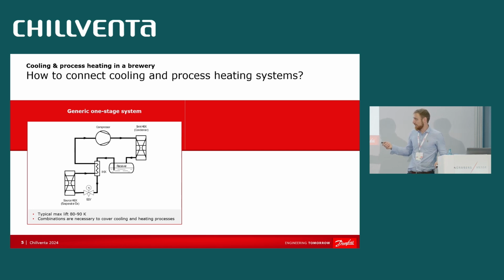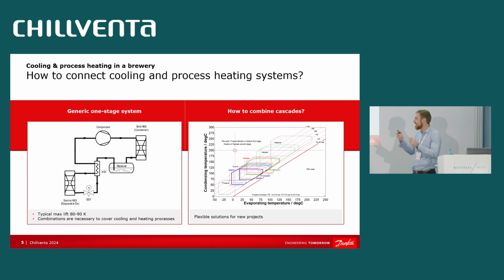And the compressors usually would give a maximum lift in one stage of 80-90 K, which basically means that with one simple, one-stage system, you can never cover both cooling and heating and definitely not generate steam. But okay, how can you do that? Then you can combine several of these one-stage systems in cascades. But which refrigerants can play a role? Here we give an example where we simulated with our compressors multiple refrigerants, a lot of hydrocarbons and some low GWP refrigerants.